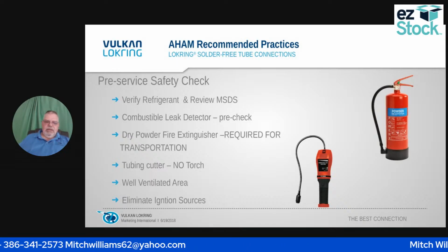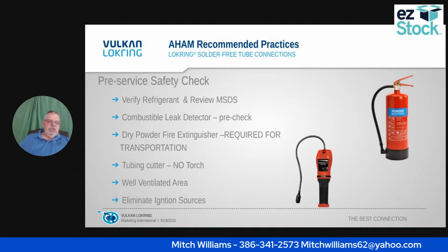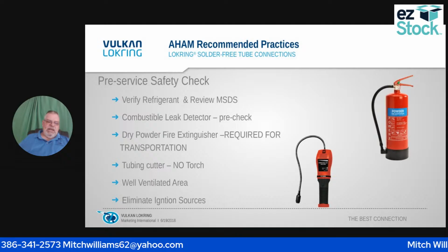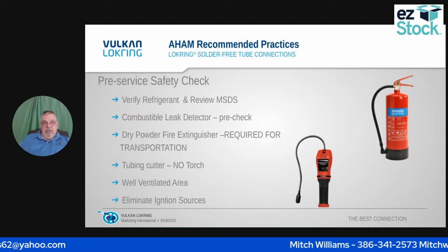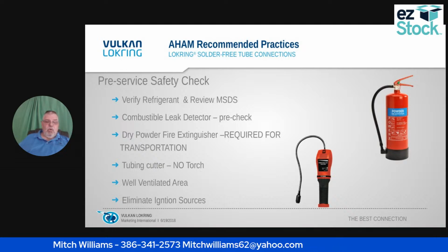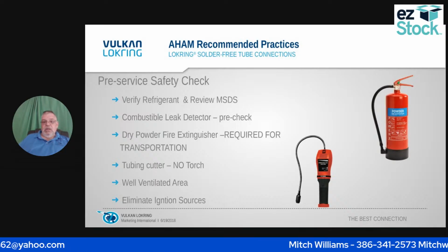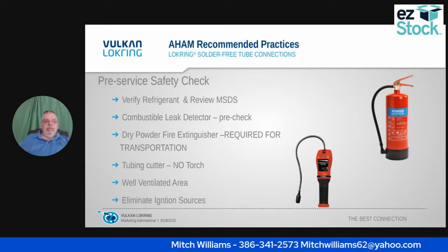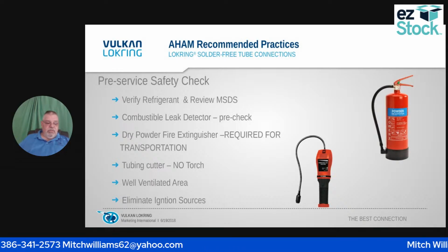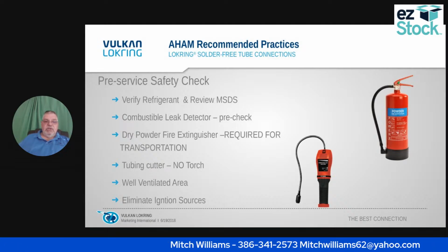No torches. If you use a torch on an R600 unit, it's not a matter of if it's going to happen. It's a matter of when it's going to happen. I subscribe to a couple of message boards, and I have seen pictures of guys whose hands were just destroyed because they had an ignition while using a torch. You can't use a torch with R600. You're just going to have problems sooner or later. I guarantee you.